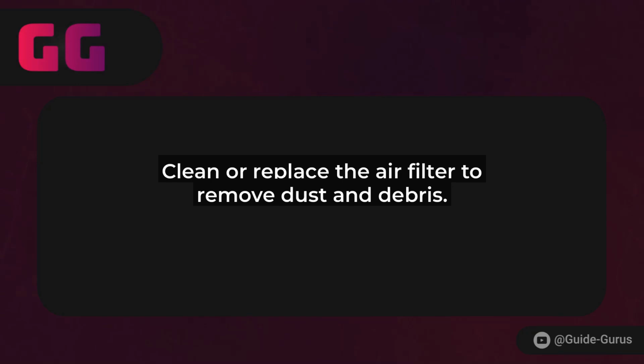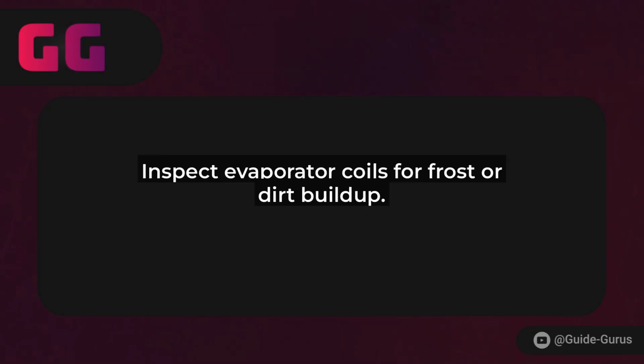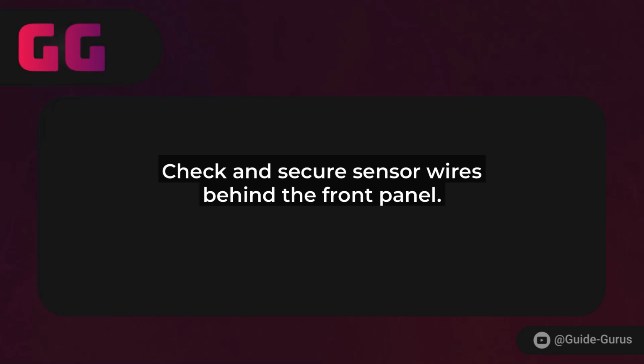Now, inspect the evaporator coils. These are usually behind the front panel. Gently remove the panel and look for any frost buildup or dirt. If you see frost, the unit might be low on refrigerant, which means it's time to call an expert. While you're in there, ensure the sensor wires are securely connected, no loose ends.